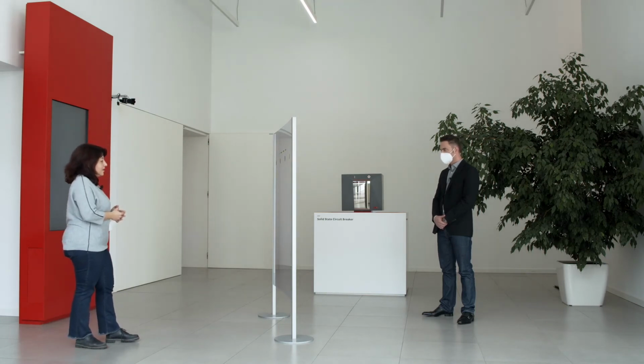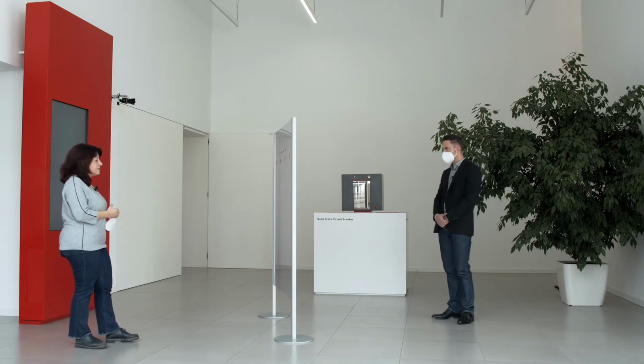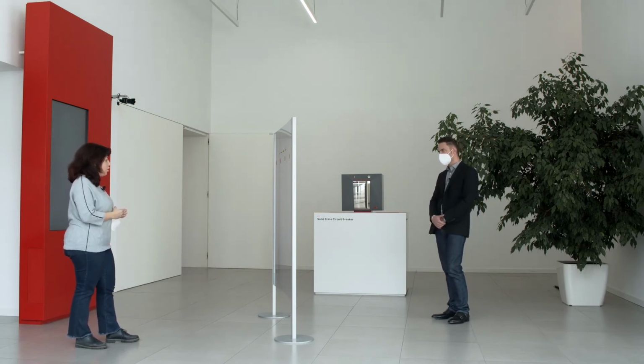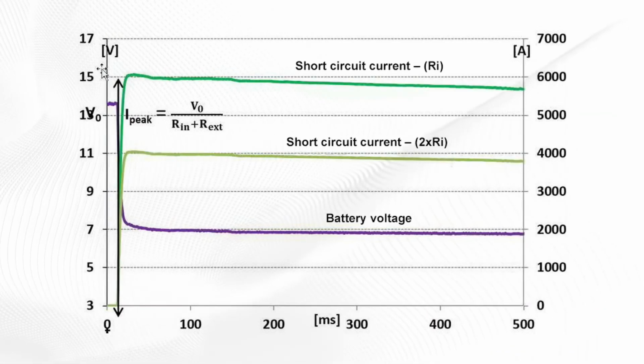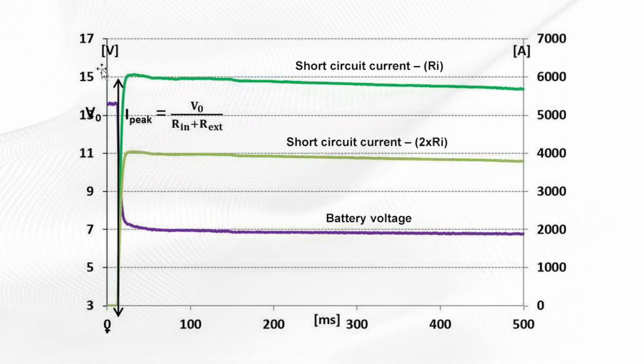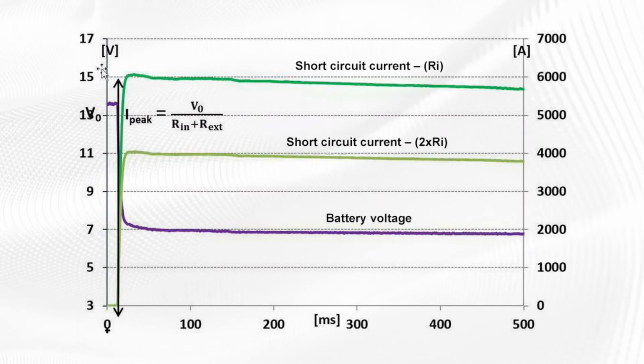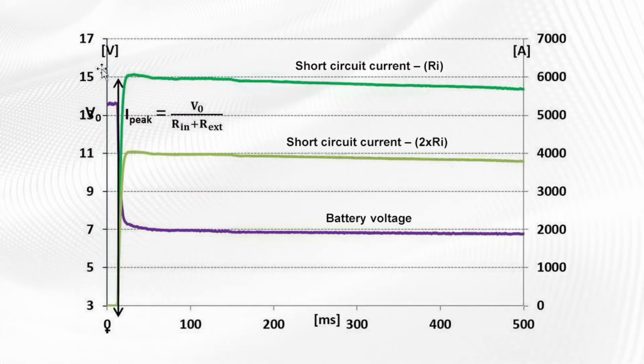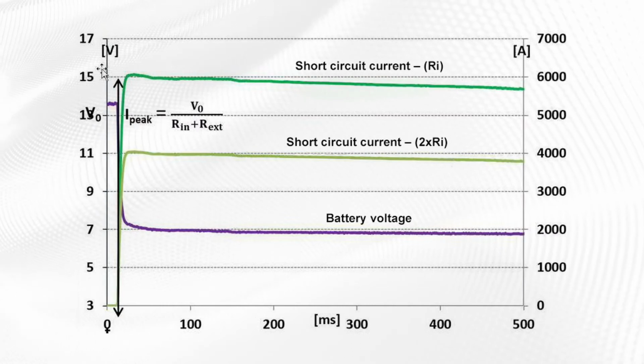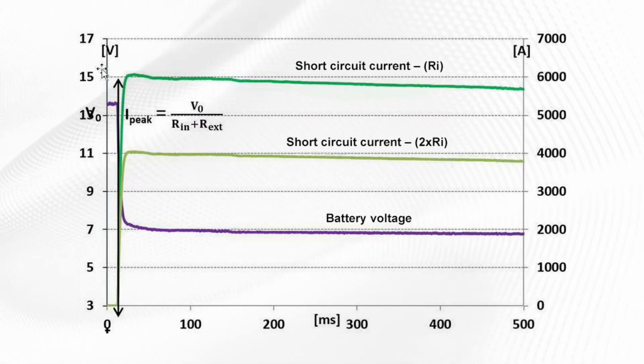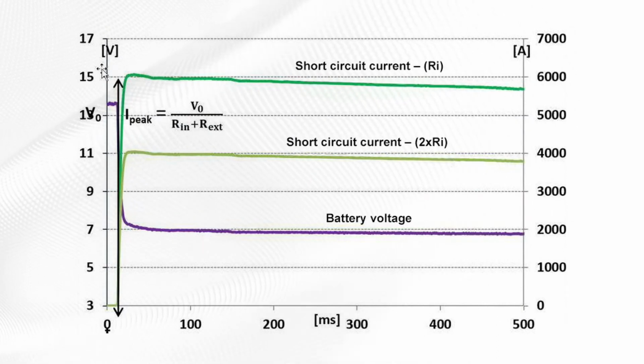The study of the short circuit current of the battery is very important during the design of the energy storage system and during the sizing of the protections and the elements of the system. During the fault, the current of the accumulator reaches the peak current almost immediately. Then the value of the current gradually decreases for a few seconds.